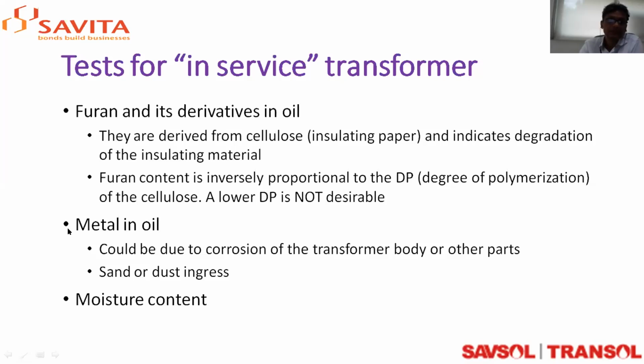So normally, when you take new paper, the degree of polymerization is around 1200 to 1250. But whenever there is aging of the paper, the degree of polymerization reduces from 1200 to, let's say, around 200 to 250. Normally, everybody in the transformer oil industry knows that when it goes below 250 or so, you have to consider that the paper is now fully degraded, and you have to go for replacement of the transformer or think of certain remedies other than that.